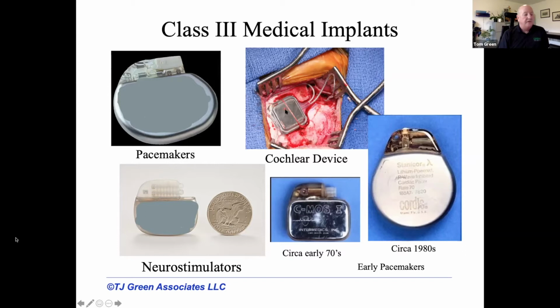And many of them contain a silastic overcoat, which is also a little bit problematic when you try to employ a conventional leak test methodology. But these are the kind of devices I have in mind. Now, dating back to the early 70s and into the 80s, in some ways, the devices haven't changed all that much. Cordis was a leader, but even back then, they had some kind of molded epoxy header over the hermetic feed-throughs. But from the very early days, the medical device community really borrowed from the military qualification and specification system.